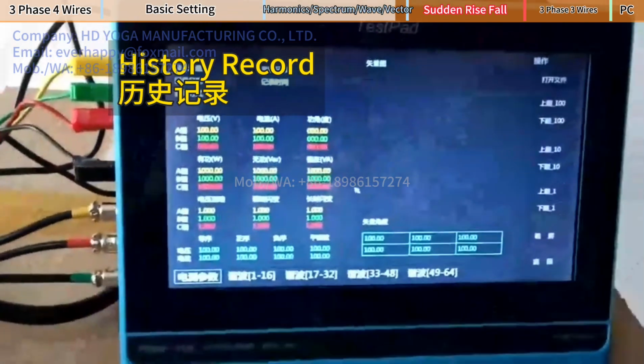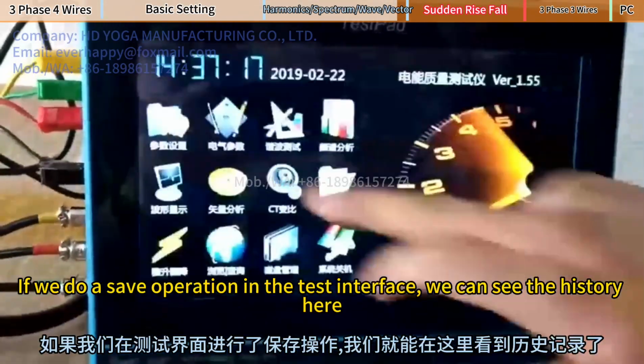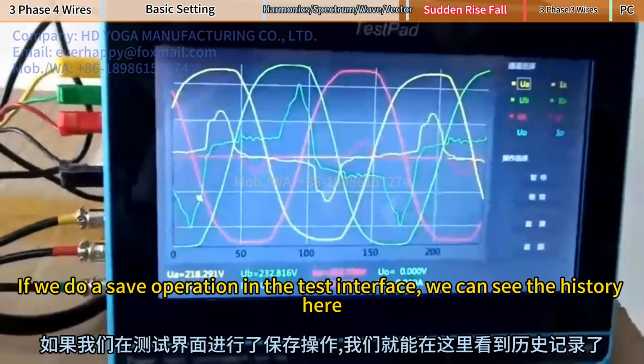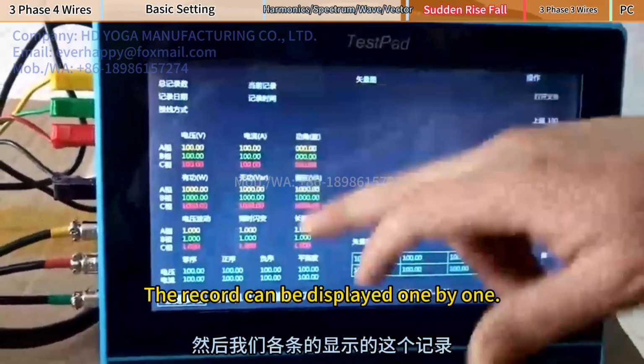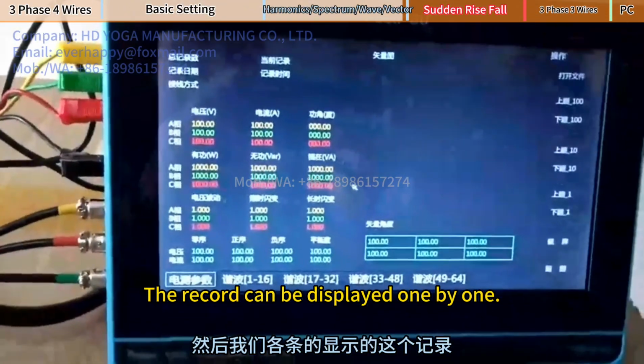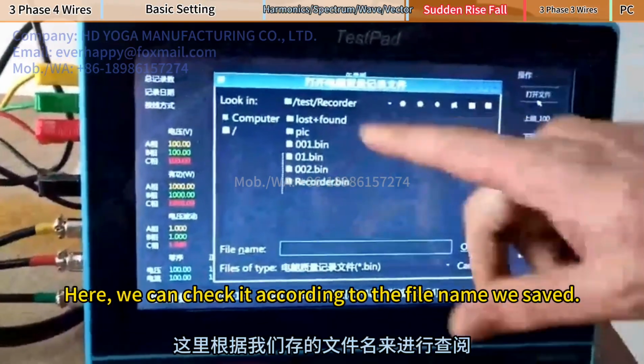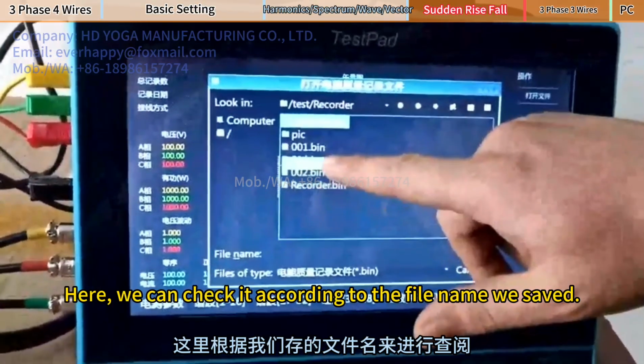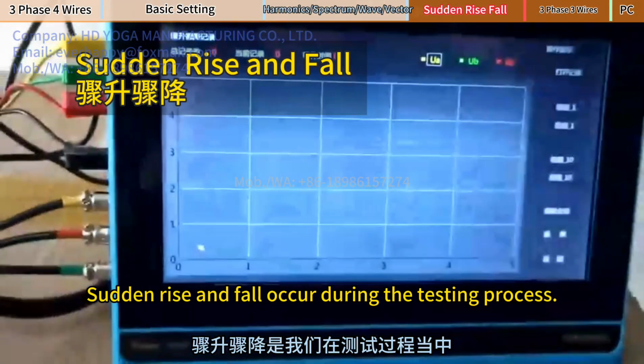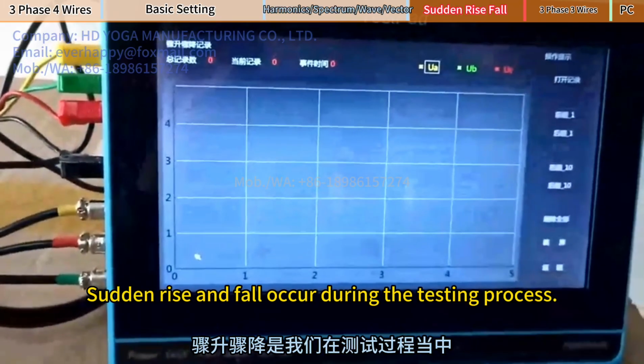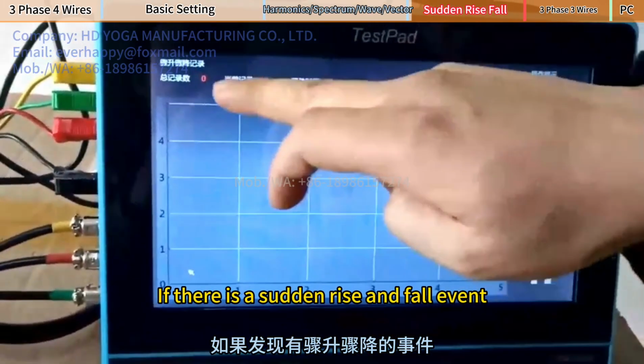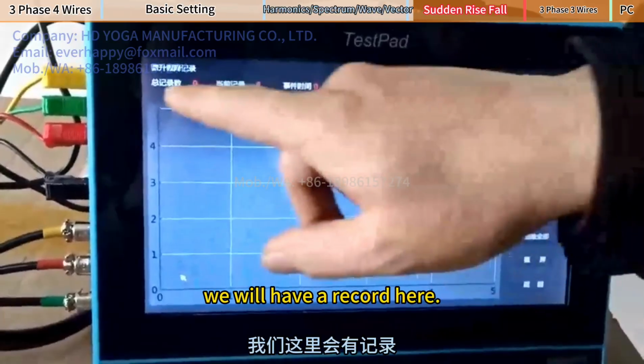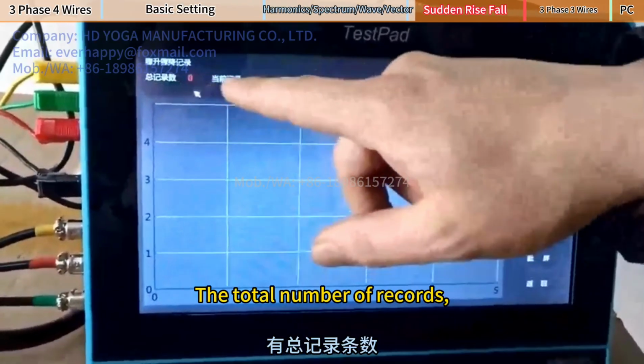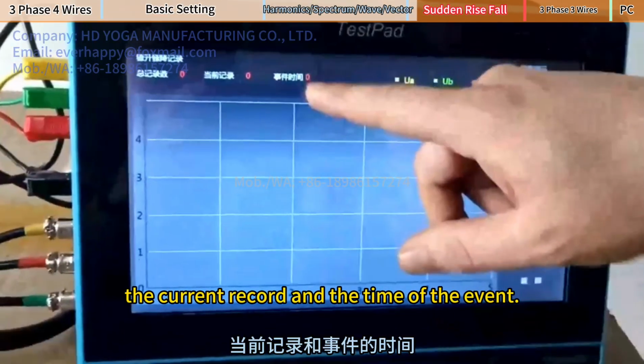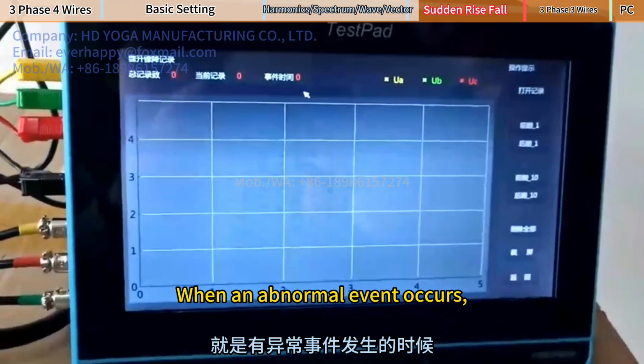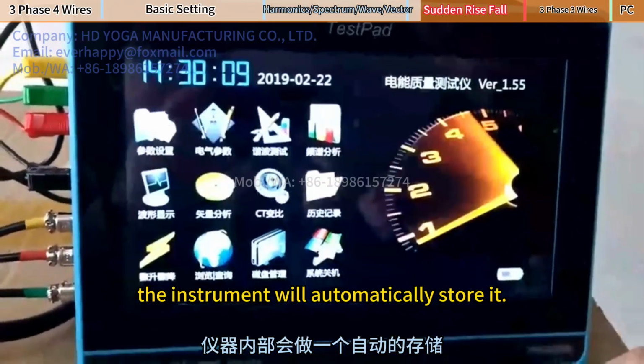Historical records. If we do a save operation in the test interface, we can see the history here. The records can be displayed one by one. Click to open the file. Here, we can check it according to the file name we saved. Sudden rise and fall events may occur during the testing process. If there is a sudden rise and fall event, we will have a record here: the total number of records, the current record and the time of the event. When an abnormal event occurs, the instrument will automatically store it.